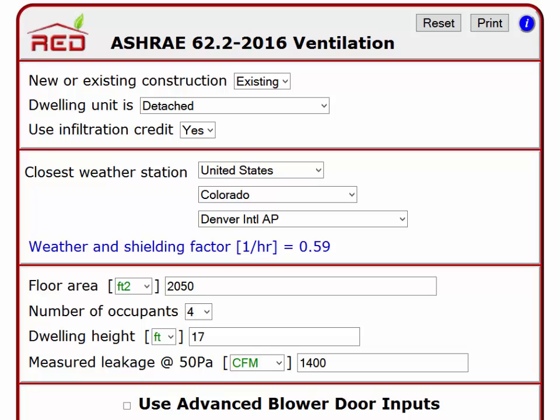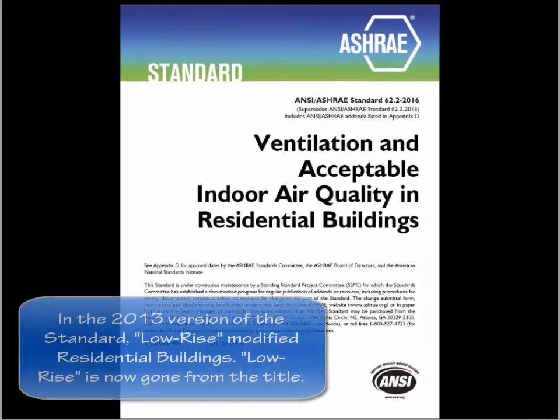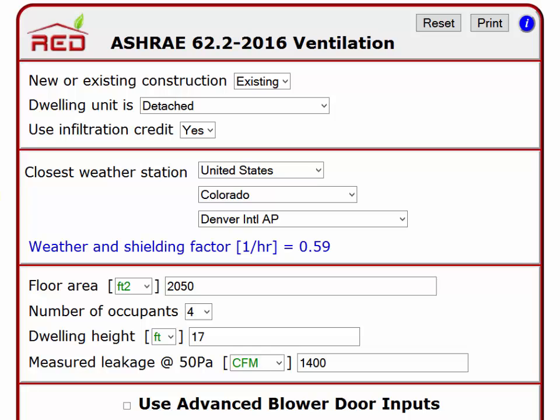There really aren't very many changes to discuss, but I want to make sure those of you that know the 2013 version well can watch this video and very quickly find out what the changes are. The biggest change to the ASHRAE 62.2 2016 standard is the inclusion of multi-family buildings of any height. The 2013 version included multi-family buildings of three stories and fewer. That change has brought a number of terminology changes and other things, though the changes to the RED tool are not as significant.